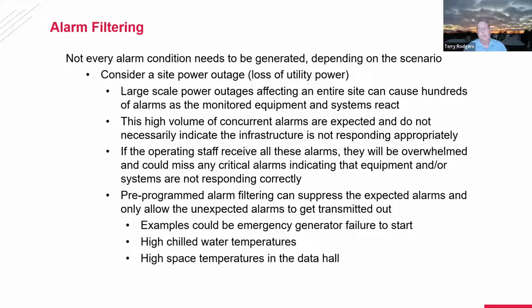Alarm filtering is another capability most of these BMS systems have, but one that I see is often not taken advantage of. It takes some programming and some finesse on the people who set up and program these systems. But in some anomalies, especially in a data center, when you take a complete power outage to the building, you expect a lot of things to occur. You're going to have a lot of equipment fail from loss of power, and that's going to generate a lot of alarms. Then you're going to have a lot of activity in the electrical system as the UPSs continue to supply power, the generators start, and the switchgear transfers over to generator power. And then you're going to see the chill water plant come back to life. And so now all these alerts are coming in of equipment being restarted, et cetera.